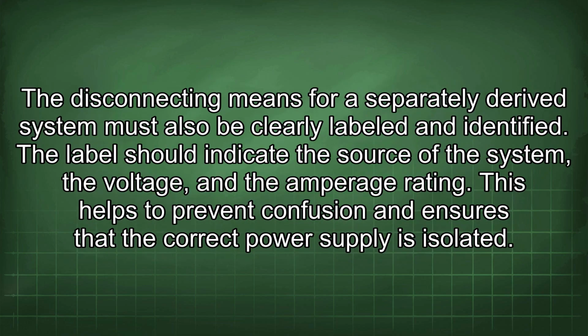The disconnecting means for a separately derived system must also be clearly labeled and identified. The label should indicate the source of the system, the voltage, and the amperage rating. This helps to prevent confusion and ensures that the correct power supply is isolated.